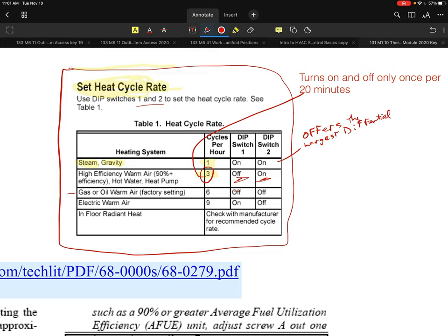For an electric warm air furnace, you can cycle it almost as much as you want. They suggest nine times per hour — dip switch one on, dip switch two off. An electric furnace basically just enables a fan on every heating demand and uses contactors to turn the electric resistance heating on and off, so high cycling isn't a problem.